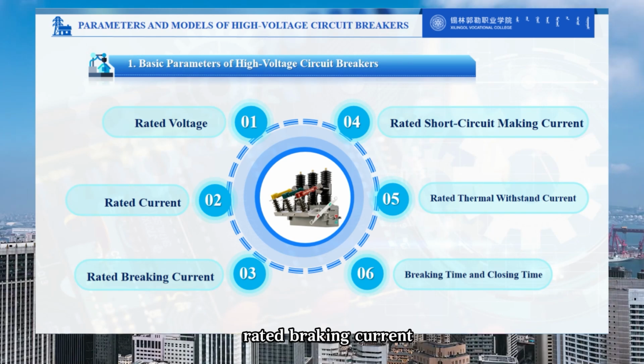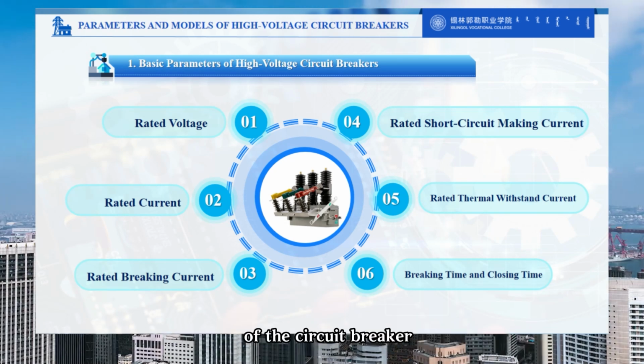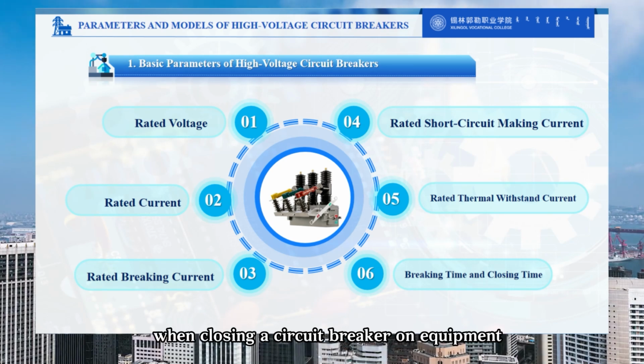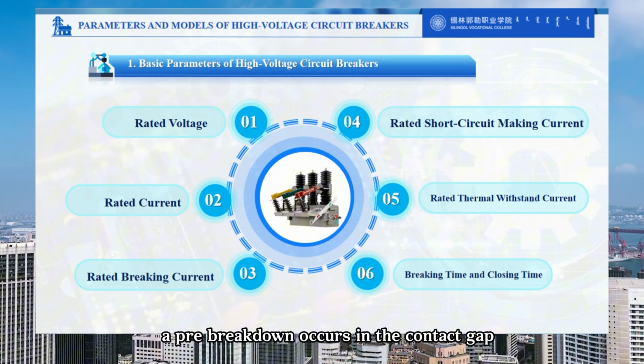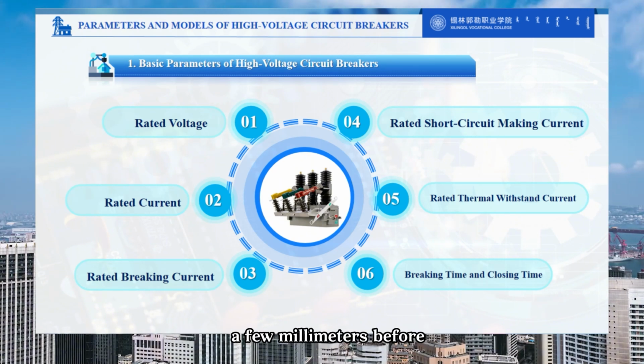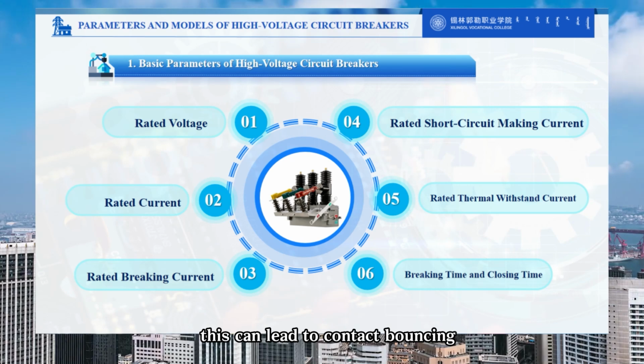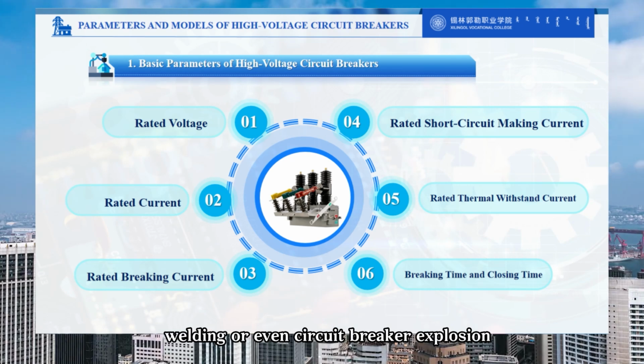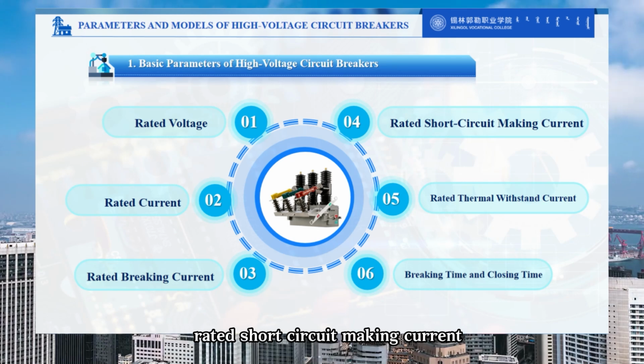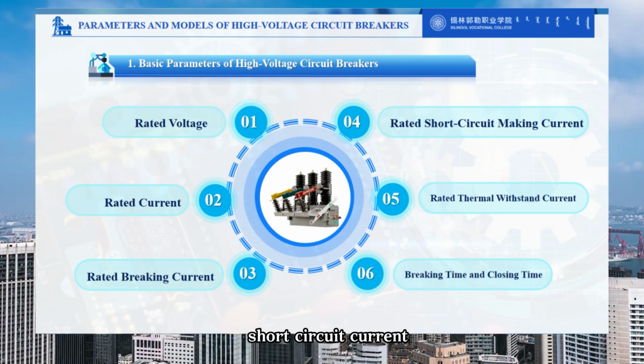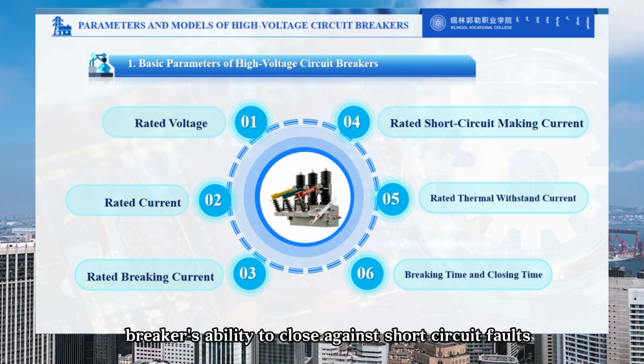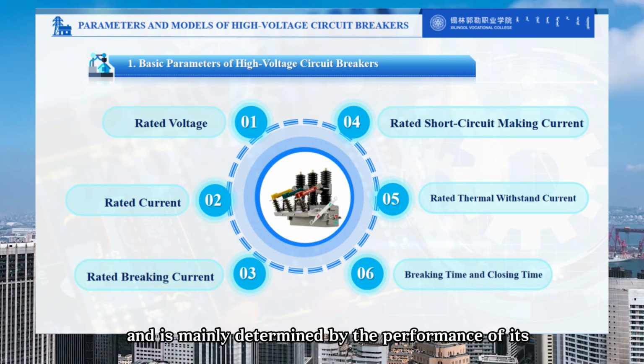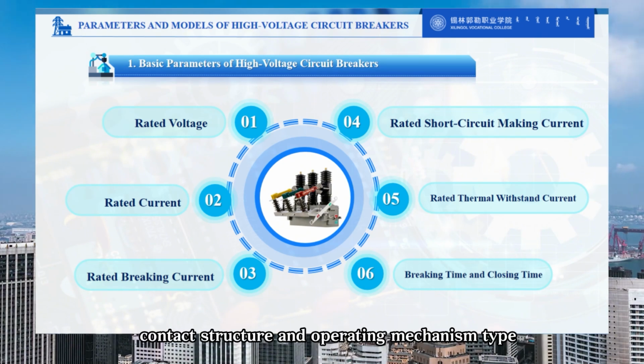Rated breaking current refers to the effective value of the maximum short-circuit current that the circuit breaker can normally interrupt at rated voltage. It represents the interrupting capability of the circuit breaker when closing a circuit breaker on equipment with a pre-existing fault. A pre-breakdown occurs in the contact gap a few millimeters before the moving and stationary contacts touch. This can lead to contact bouncing, welding, or even circuit breaker explosion. Rated short circuit making current refers to the peak value of the maximum short circuit current that the circuit breaker can make under such conditions. It reflects the circuit breaker's ability to close against short circuit faults and is mainly determined by the performance of its arc extinguishing device, contact structure, and operating mechanism type.